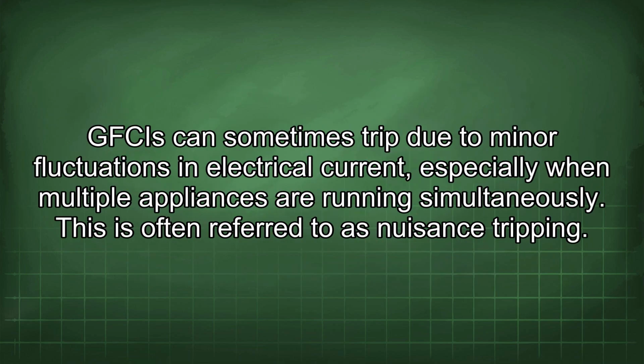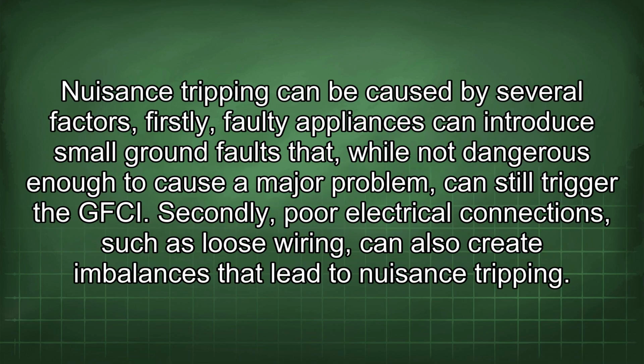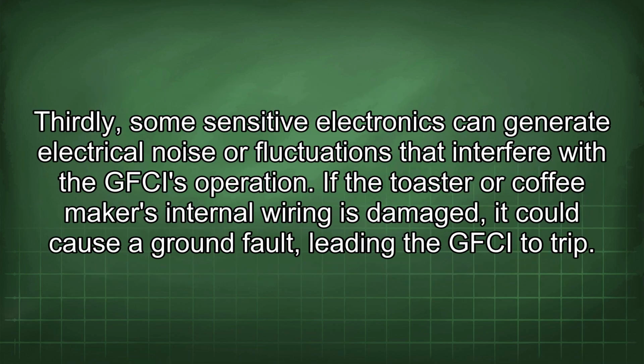GFCIs can sometimes trip due to minor fluctuations in electrical current, especially when multiple appliances are running simultaneously. This is often referred to as nuisance tripping. Nuisance tripping can be caused by several factors. Firstly, faulty appliances can introduce small ground faults that, while not dangerous enough to cause a major problem, can still trigger the GFCI. Secondly, poor electrical connections, such as loose wiring, can also create imbalances that lead to nuisance tripping. Thirdly, some sensitive electronics can generate electrical noise or fluctuations that interfere with the GFCI's operation.